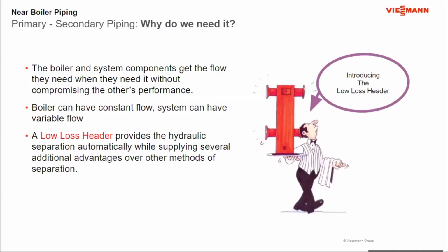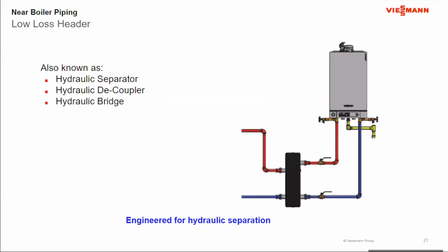Okay. Now, when I do primary secondary, one of the piping options that are available is what's called a low loss header. Okay. So the low loss header really is a pre-engineered hydraulic separator. So I put this in the system. I don't worry about the 4 pipe diameters of spacing. The design of the low loss header gives me that hydraulic separation. Okay. And the other thing is with this hydraulic separation, there's a couple other advantages that it brings to the table. Now, we're saying low loss header. You may have heard low loss headers also referred to as hydraulic separators, hydraulic decouplers, or even hydraulic bridges. They're all the same thing.